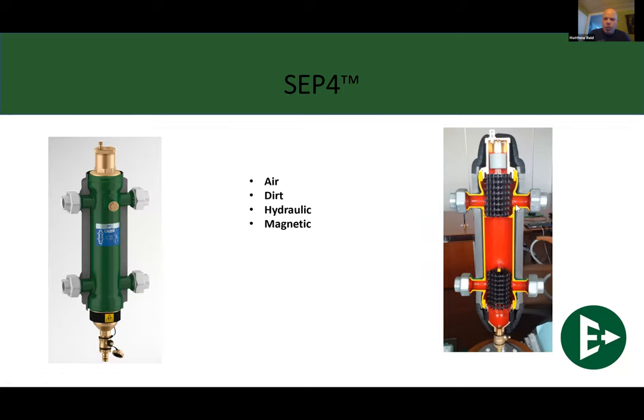So this is the same material inside the hydro sep that's built inside the air separator. Still is that exact same media. I think their specifications say that this pulls out, I believe it's 90 plus percent of all oxygen in the system in its first pass. Same as the dirt separator, pulls out 90 plus percent of all dirt in the first pass. The hydro separator, the one from Caleffi anyway, is built at the exact same specifications as the individual pieces.